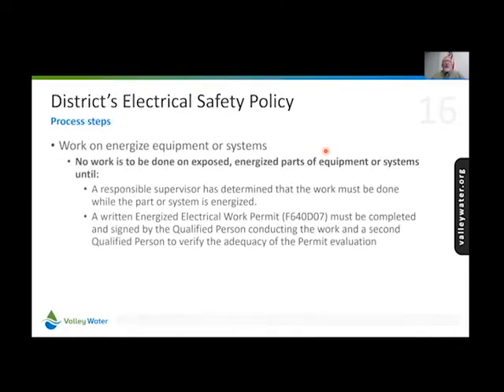For work on energized equipment or systems, no work is to be done on exposed energized parts until a responsible supervisor has determined the work must be done while the part or system is energized. A written energized electrical work permit must be completed and signed by the qualified person conducting the work and a second qualified person to verify the adequacy of the permit evaluation.